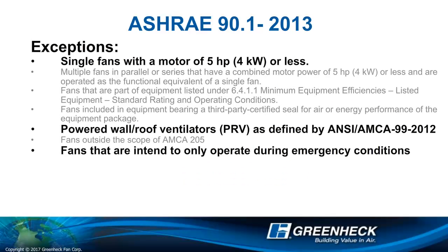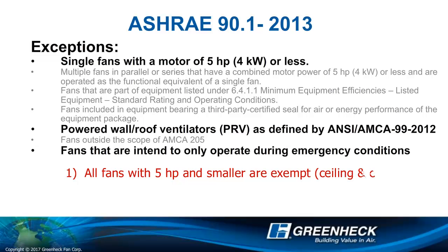There are many exceptions. We will focus on the three main exceptions related to Greenheck products. First, single fans with a motor of 5 horsepower or less — in other words, all fans under 5 horsepower are exempt. This means all Greenheck ceiling and cabinet fans are exempt, as none of these have 5 horsepower motors.